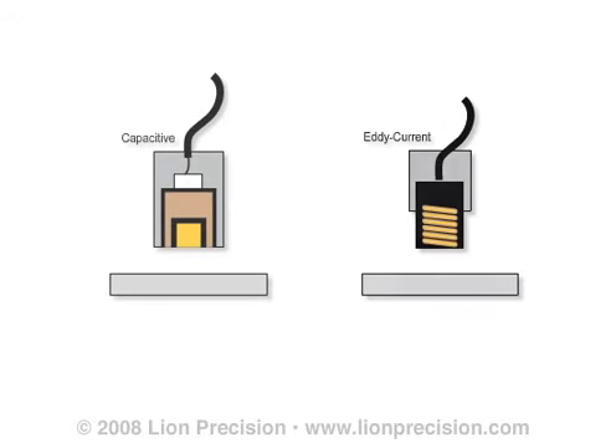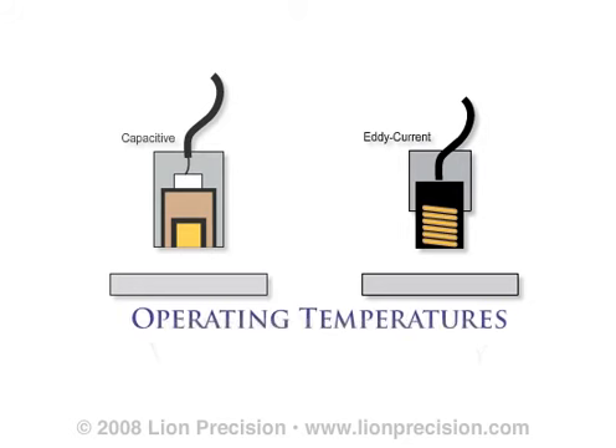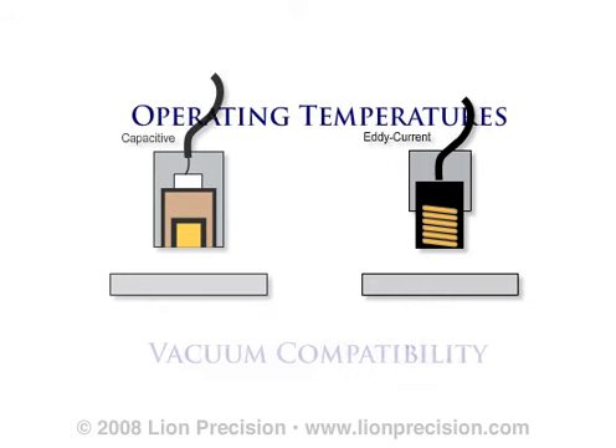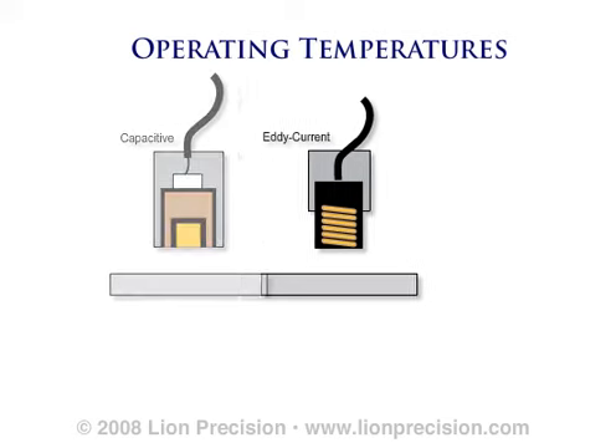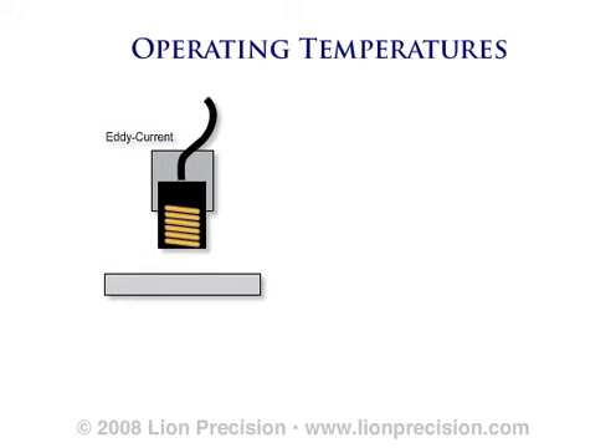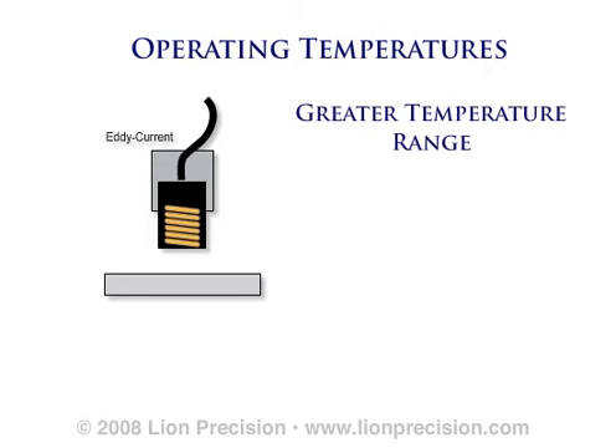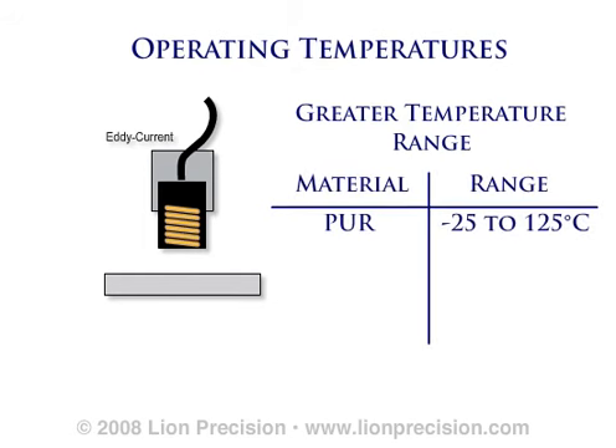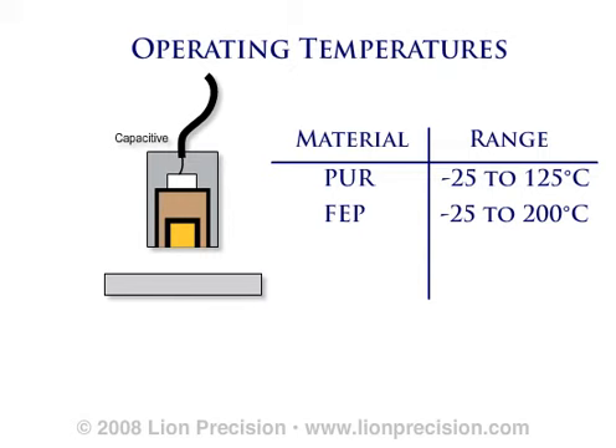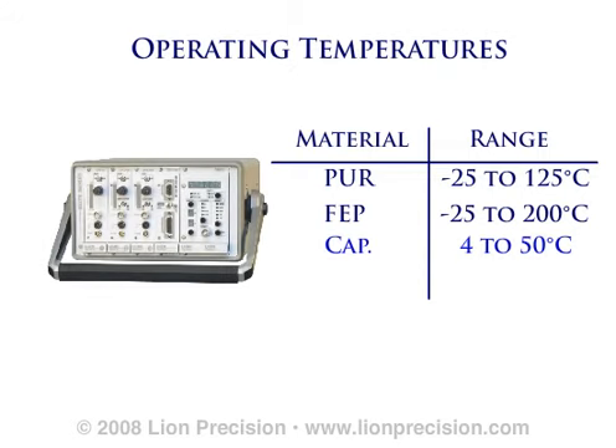Because of differences in the sensing physics and the associated differences in driver electronics, capacitive and eddy current sensors have different probe operating temperature ranges and vacuum compatibility. Precision capacitive and eddy current probes have different operating temperature ranges. Eddy current probes, because of their tolerance of hostile environments, have a greater temperature range. Standard eddy current probes, which use polyurethane cables, have an operating range from -25 to +125 degrees C. High temperature probes, which use Teflon FEP cables, have an operating range of -25 to +200 degrees C. Capacitive probes, which are affected by condensation, only have an operating range of +4 to +50 degrees C. The driver electronics for both sensing technologies have an operating range of +4 to +50 degrees C.